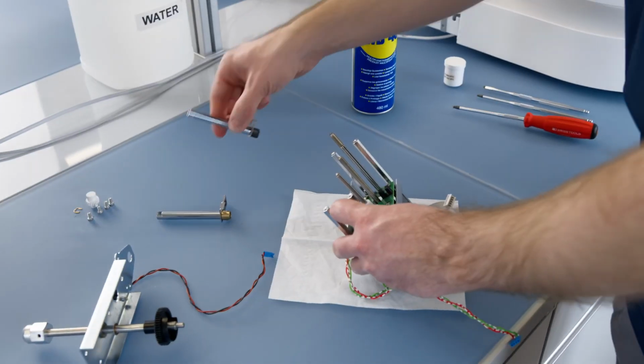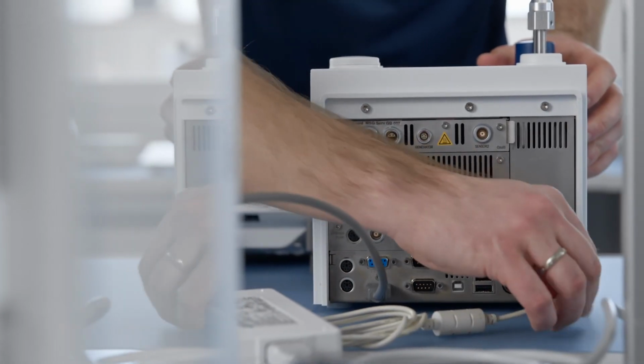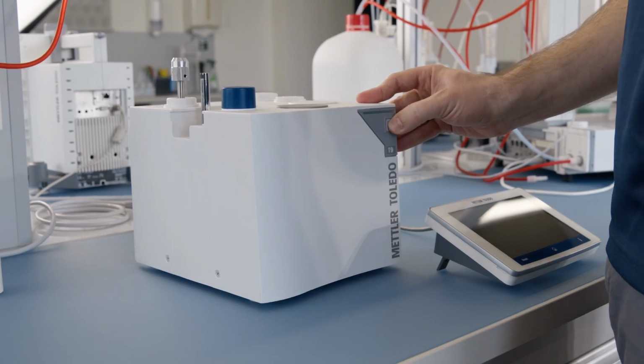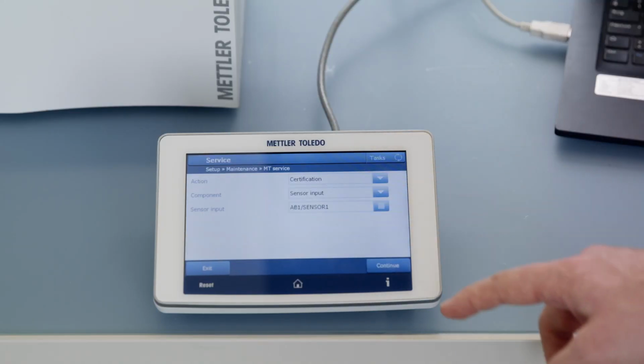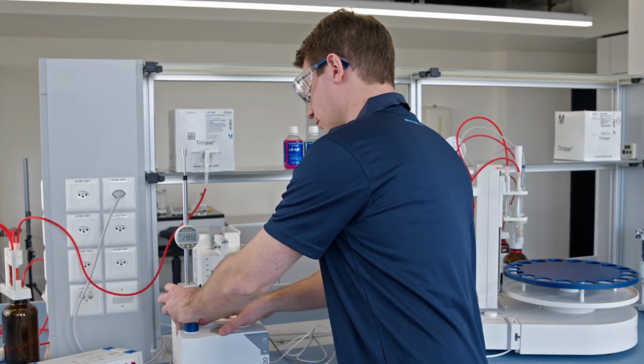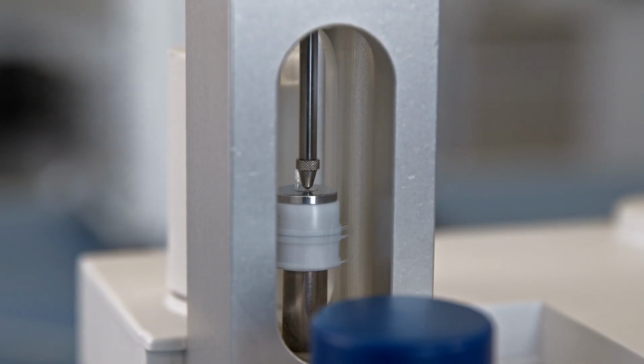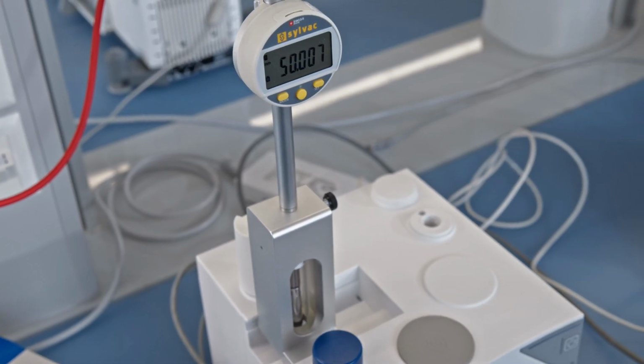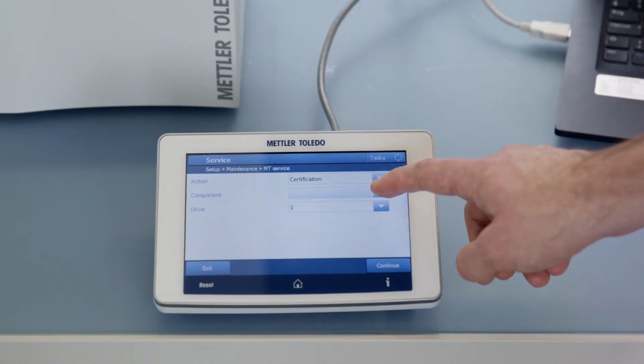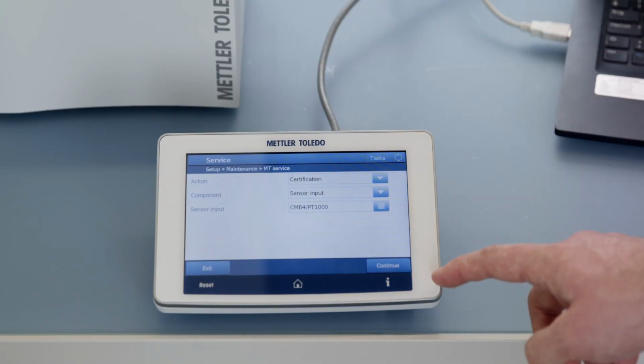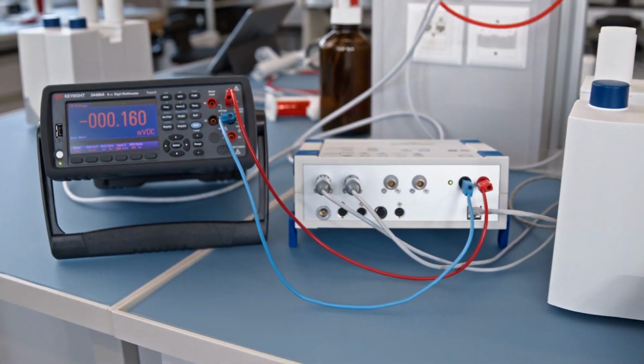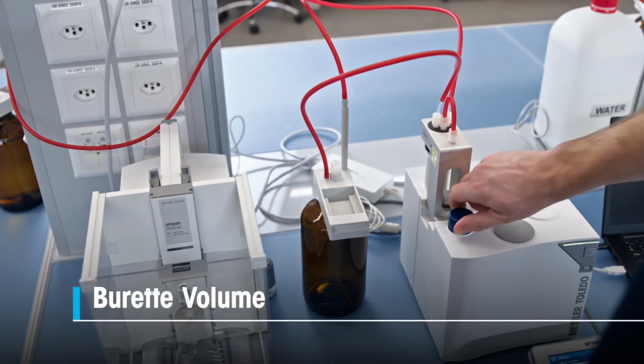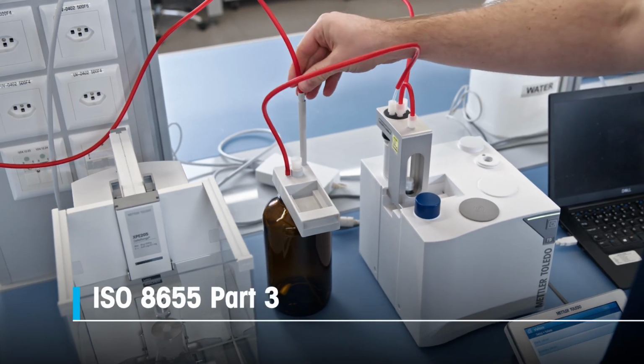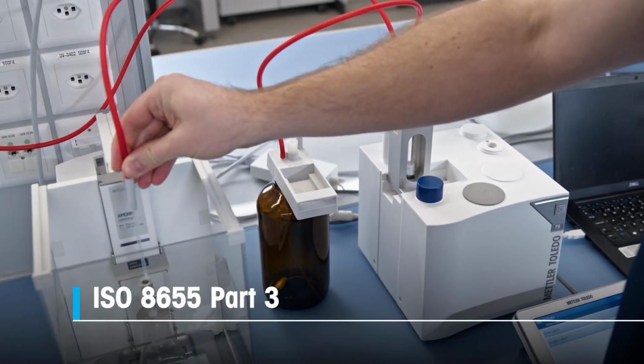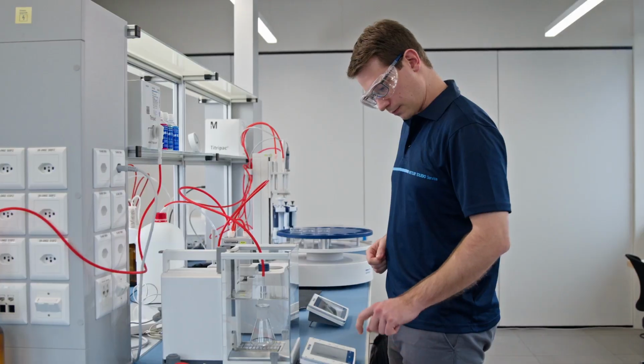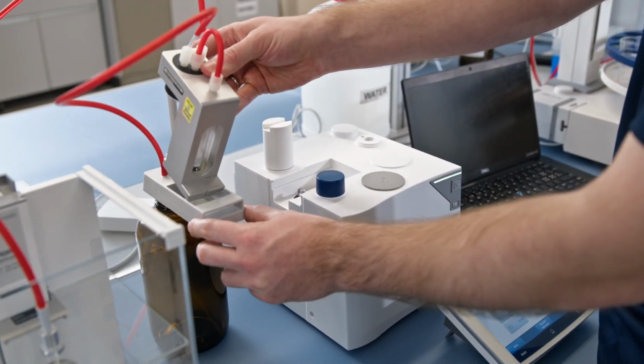assure a smooth movement. After preventive maintenance, a calibration of the major components is performed. This is the burette drive piston stroke length to ensure dosing accuracy, as well as all sensor inputs to assure correct monitoring of the titration. The burette volume is calibrated individually in accordance with ISO 8655 Part 3, using a bespoke METTLER Toledo comparative method.